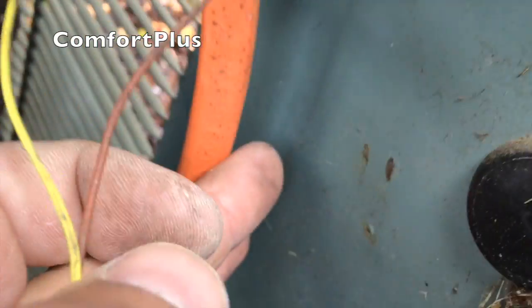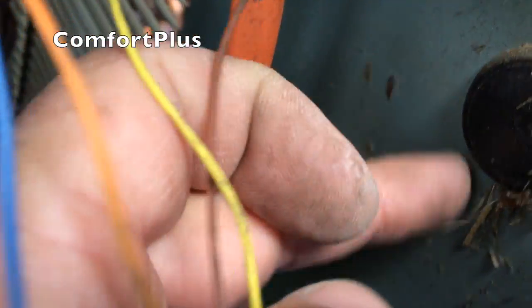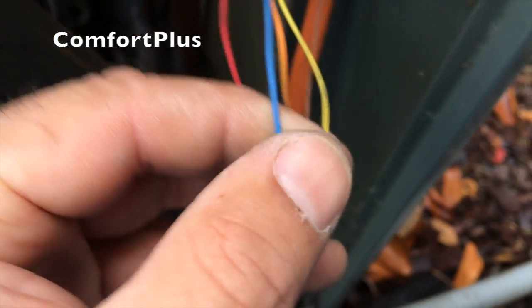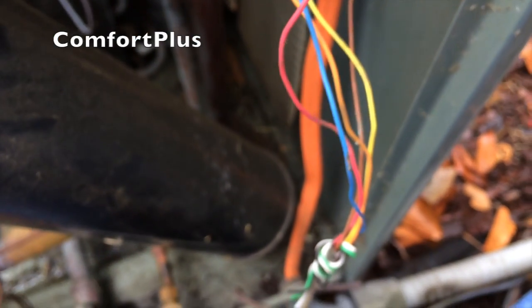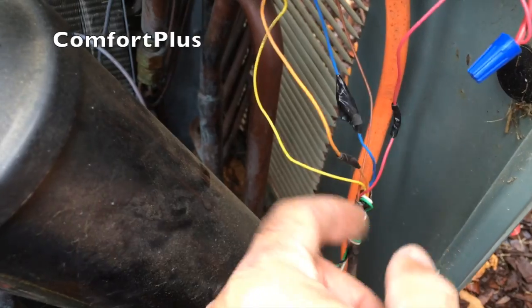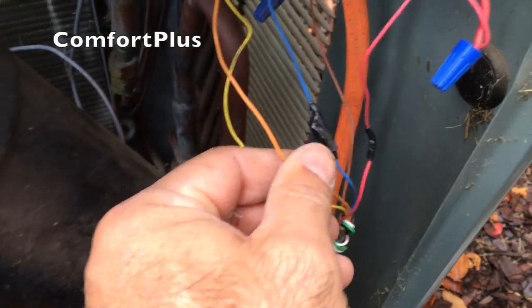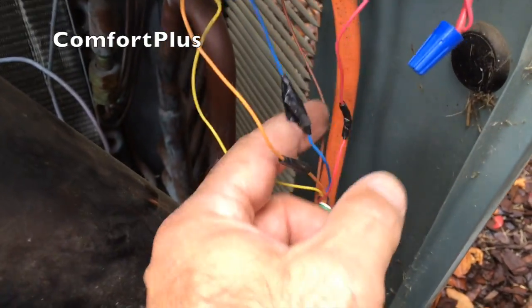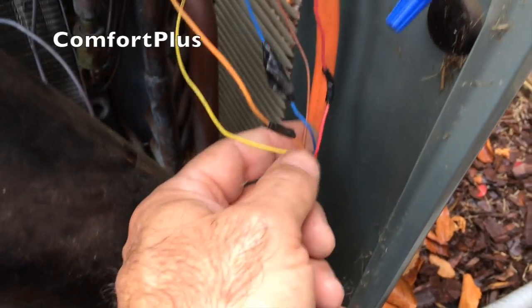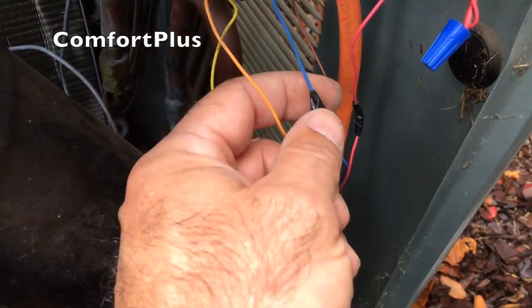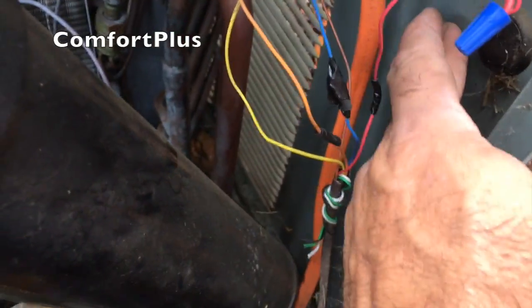It was rubbing over here against the unit, looks like. So I'm going to take that up, pull it over out of the way, bolt the defrost board back in, start it up and check it out. The red was chafed a little bit too, and the orange had a nick in it, all of it about the same place along the wire. Almost like it had been nicked when the original insulation was stripped back off the wire. And then of course rubbing against this didn't help.